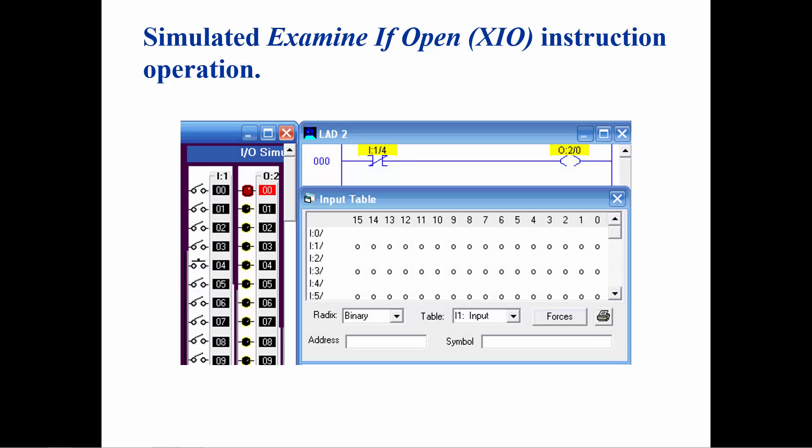When the switch is open, a 0 is placed in the input table. The examine if open will interpret this condition as true and will allow rung continuity, much like a normally closed relay contact will allow current flow when its coil is not energized. The address of the contact turns yellow, indicating logic continuity.